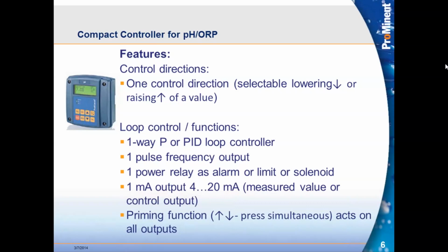It also offers something that's very nice. We'll talk about the buttons on the front. But if you press the up and down arrows at the same time, if we are taking advantage of a control output, it's going to ramp the controls to their maximum. So the pulses would come out at whatever the maximum rate is that we've determined. We tell it what pump we're pumping with. So if it's a gamma L pump or a beta pump, 180 strokes per minute. If it's maybe a sigma pump, the maximum speed on that might be 200, or even a delta pump can be 200.